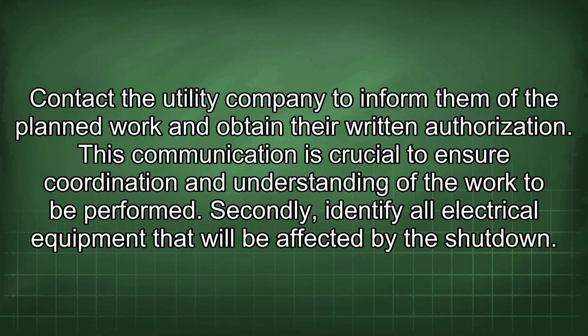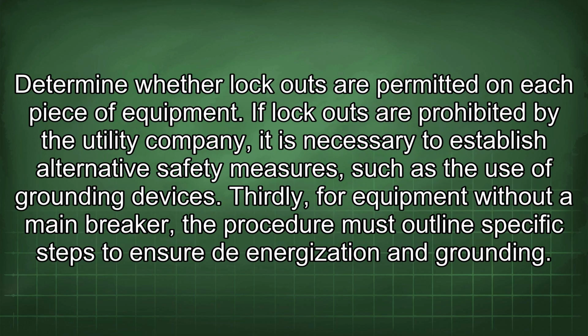Secondly, identify all electrical equipment that will be affected by the shutdown. Determine whether lockouts are permitted on each piece of equipment. If lockouts are prohibited by the utility company, it is necessary to establish alternative safety measures, such as the use of grounding devices.